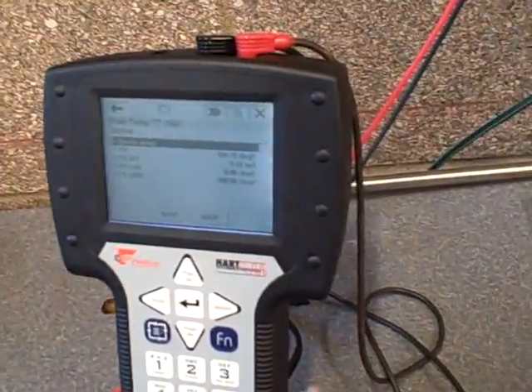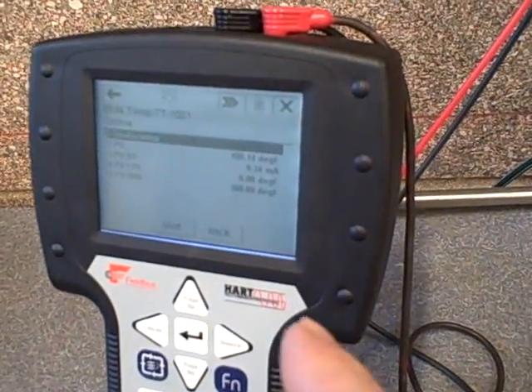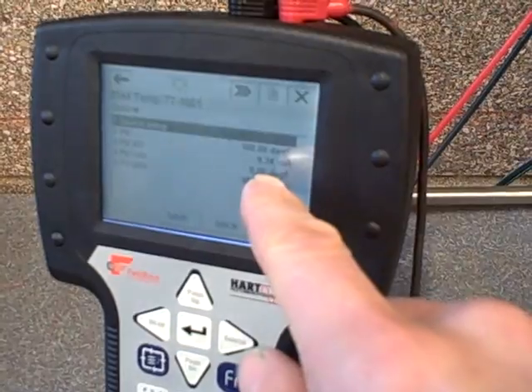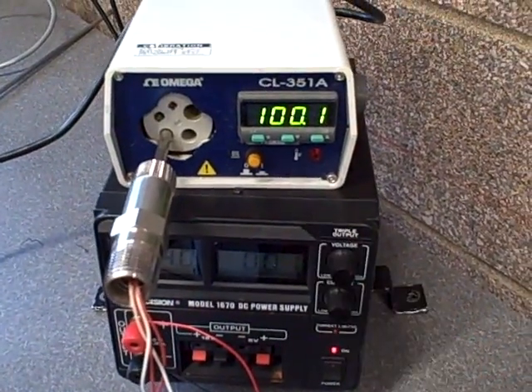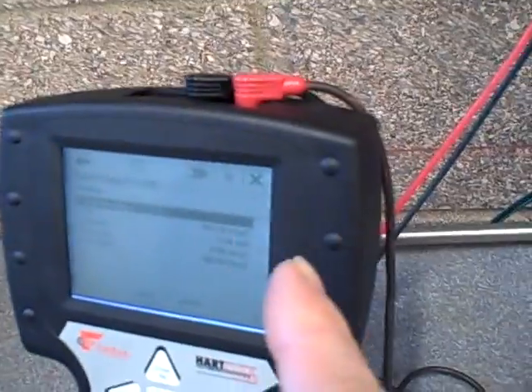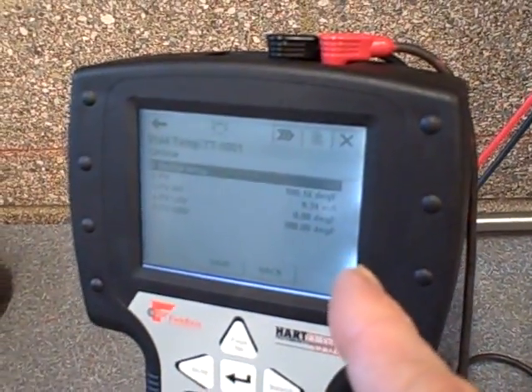We're reading the temperature, or at least what the transmitter thinks the temperature is, with the 375 smart communicator. Right now it says 100.08, 100.15, and we see 100.1 over here. So real life is in agreement with the displayed process variable value.